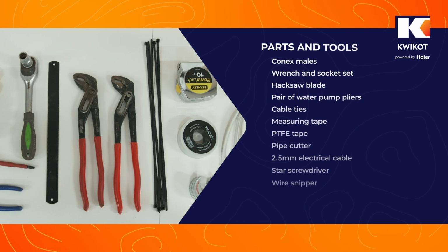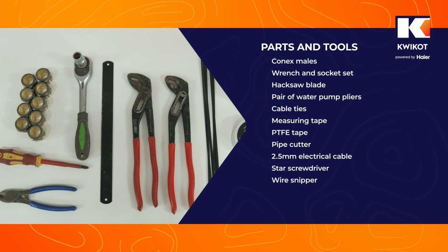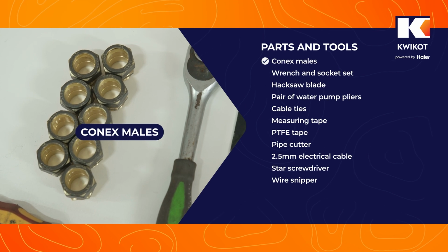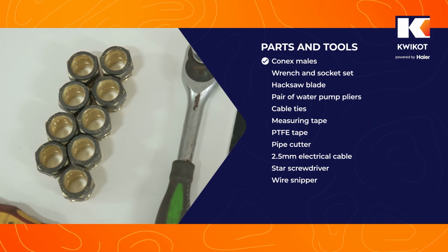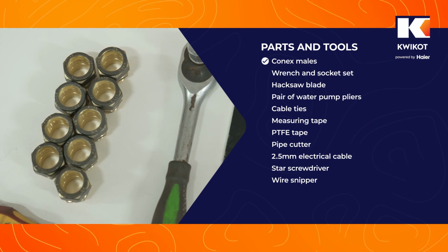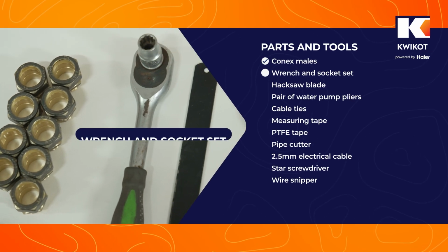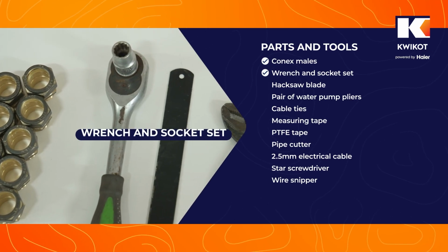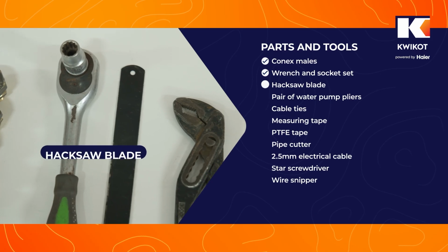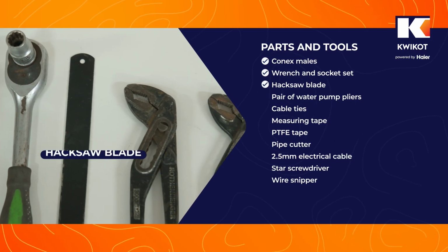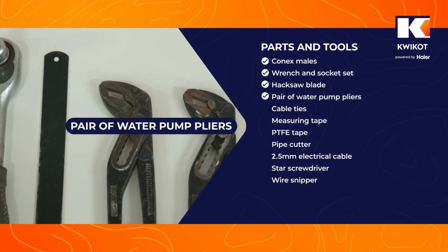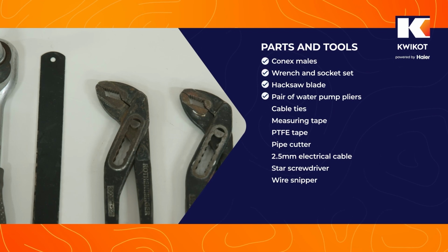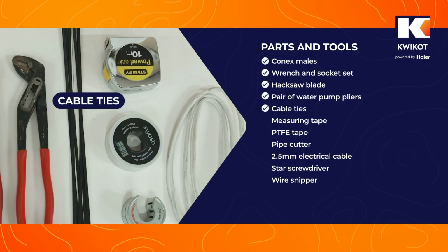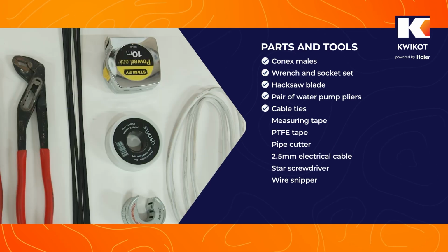You'll also need the following other parts and tools for the installation. Some Conex males for fitting both the heat pump and the water heater, and also for your ball valves and strainers. Then you'll need a wrench and socket set for fitting the brackets, and a hacksaw blade to scratch the fittings. Next we have a pair of water pump pliers that we will need to tighten the fittings, and some cable ties that will be used to secure the cable onto the pipe.